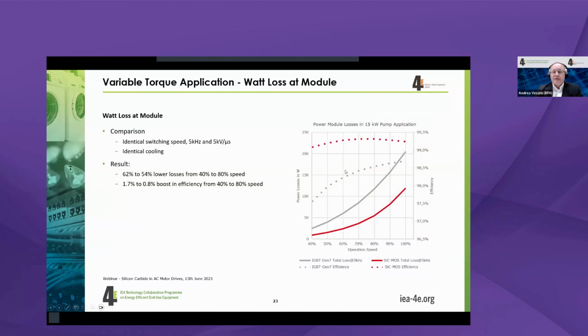And this is seen here, as you can see, the fixed line, these are the losses. So the difference between gray, that's the IGBT, and red, that's the silicon carbide, can be between 40 and 80%. Sorry, between 62 and 54%. So quite half of the losses, which has an impact on the boost of efficiency, which is between 1.7 or 0.8 better, depending on the operation speed. Now, the operation speed, keep in mind, also has a lower torque when you have lower speed.